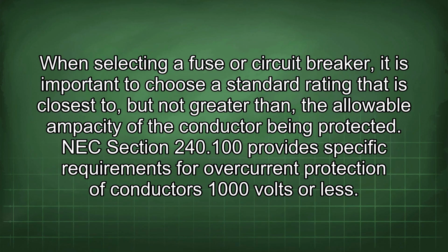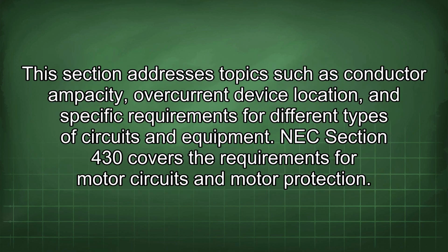When selecting a fuse or circuit breaker, it is important to choose the standard rating that is closest to, but not greater than, the allowable ampacity of the conductor being protected. NEC Section 240.100 provides specific requirements for overcurrent protection of conductors 1000 volts or less. This section addresses topics such as conductor ampacity, overcurrent device location, and specific requirements for different types of circuits and equipment.